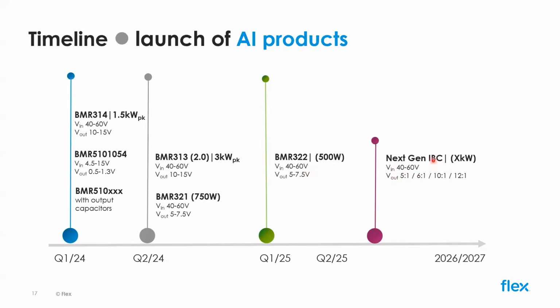And then finally, we're looking at various different ratios. We've talked about 4-to-1 and 8-to-1 — they're the most popular ratios we're discussing with customers at the moment. But there are different ratios of interest to optimize system level efficiency: 5-to-1, 6-to-1, 10-to-1, and even 12-to-1 are being requested. So we're working on topologies that can offer very simple and easy switches to these different input-to-output ratios, and the power levels will depend on those ratios. That's why it's shown here as an X kilowatt, or TBD kilowatt rating.